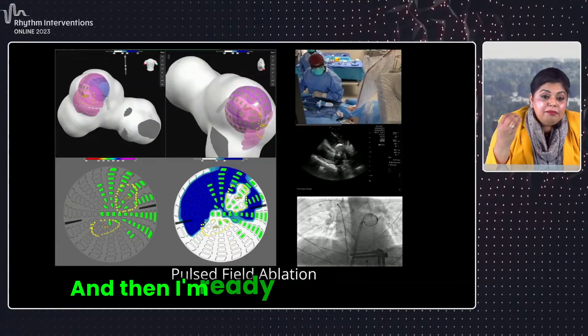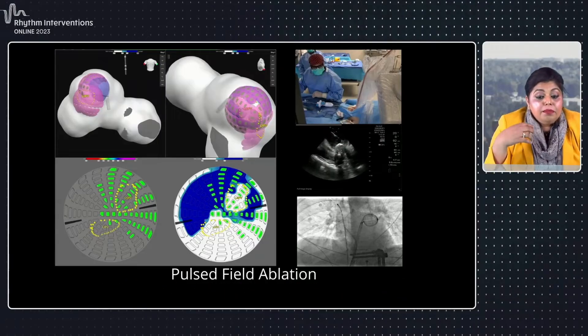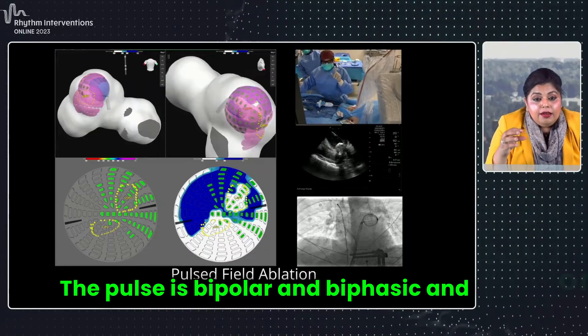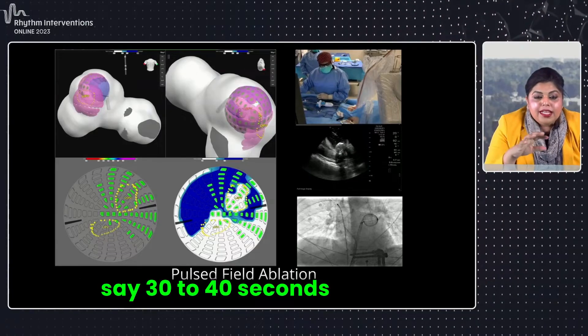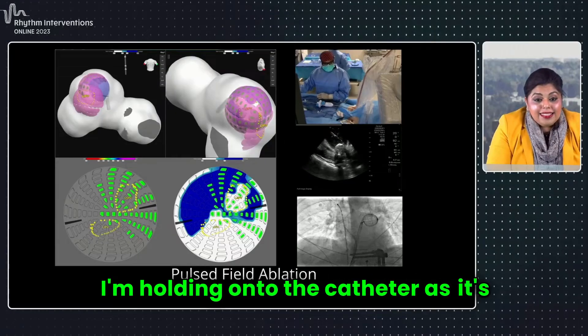And then I'm ready to deliver that pulsed field. It's that single pulse train — the pulse is bipolar and biphasic. Once we deliver that pulse, it's about 30 to 40 seconds for that whole delivery. I'm holding on to the catheter as it's happening.